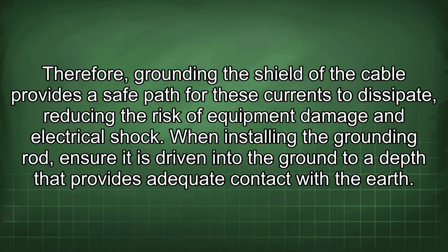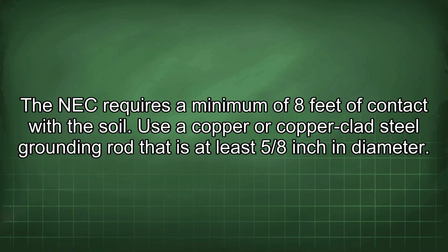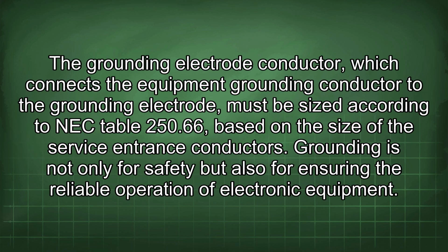When installing the grounding rod, ensure it is driven into the ground to a depth that provides adequate contact with the earth. The NEC requires a minimum of 8 feet of contact with the soil. Use a copper or copper-clad steel grounding rod that is at least 5/8 inch in diameter. The grounding electrode conductor, which connects the equipment grounding conductor to the grounding electrode, must be sized according to NEC Table 250.66 based on the size of the service entrance conductors.